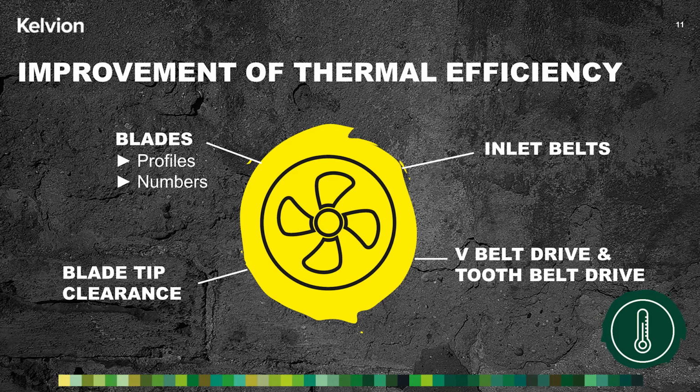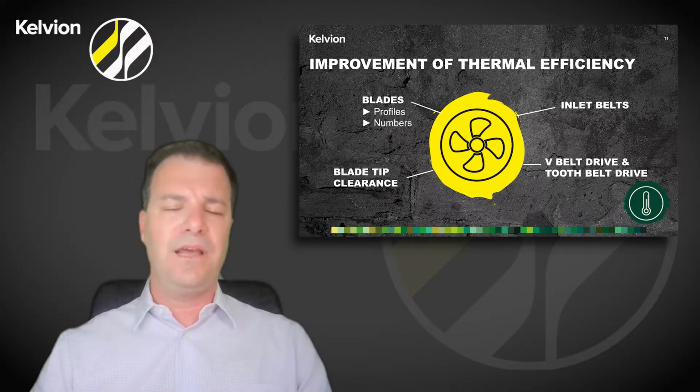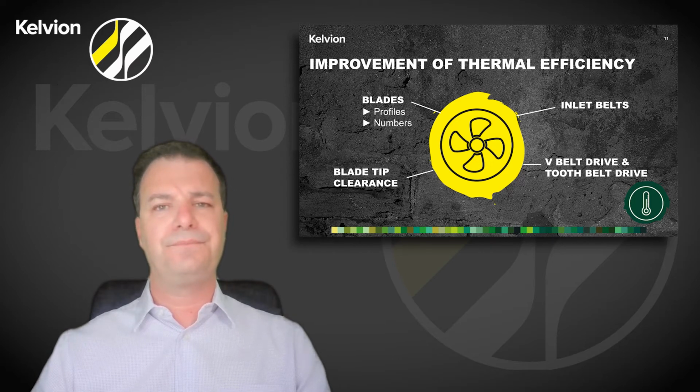With the inlet bells, you can also influence the efficiency by up to 3%. With regard to the drive, the modifications shown in the previous examples were about the fan efficiency, but it is good to remember that the fan efficiency also has high dependency on drive efficiency, and therefore this is also a key element to check as part of our audit. You can achieve different efficiency depending on going with V-belt or tooth belt drives. Last but not least, the number of blades and revolutions have to be chosen carefully as well.